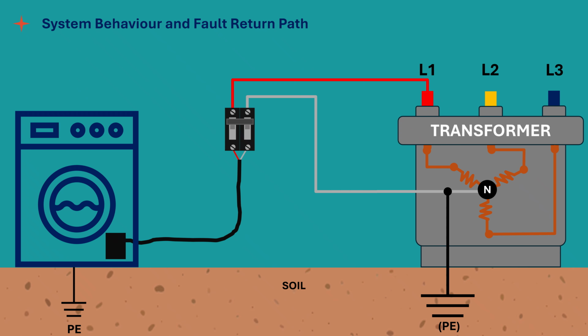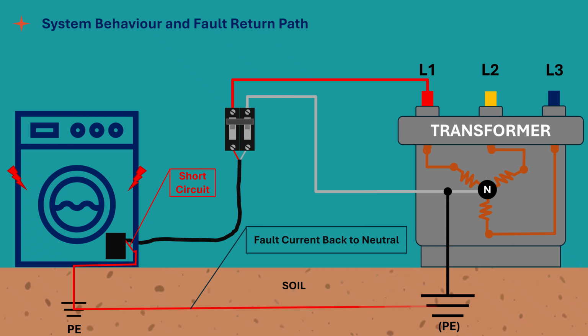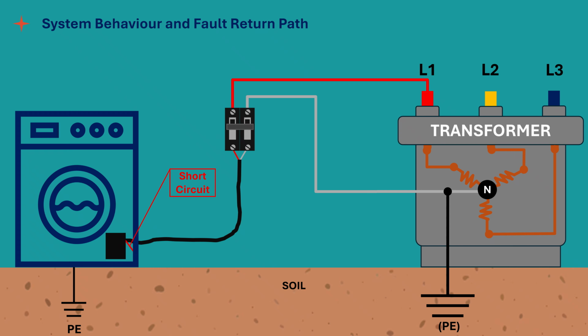Now that we've clarified the difference between earthing and grounding, let's move on to understanding how the system behaves during a fault and how the fault current return path is established. Although there are various grounding systems, fault current always returns to its source, using the earth or protective conductor only as part of the loop. So when a phase or live wire touches a metal body connected to an earth electrode, the current flows through the soil back to the transformer neutral, allowing protective devices such as MCB, MCCB, and RCD to detect the imbalance and trip the supply. Once isolated, the short circuit fault must be located and cleared so the equipment can be safely returned to normal operation.